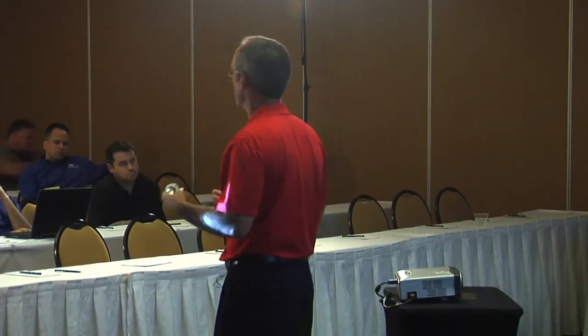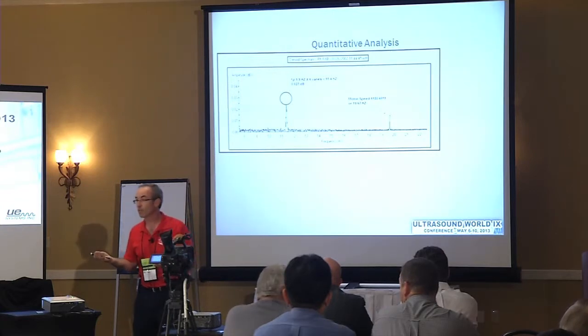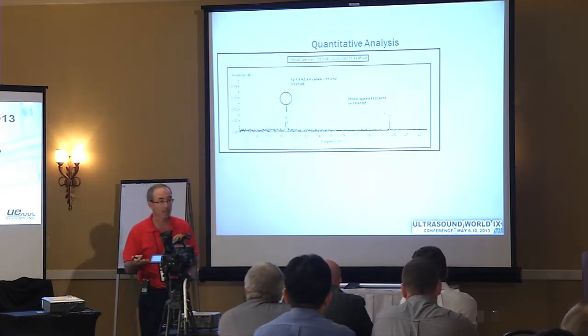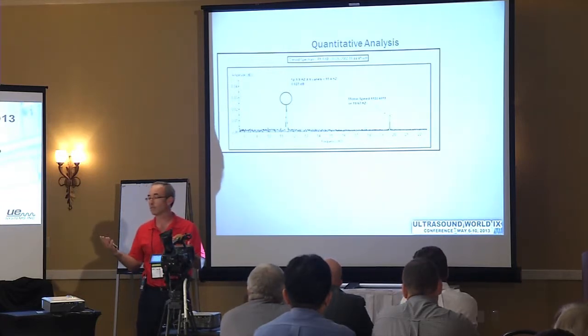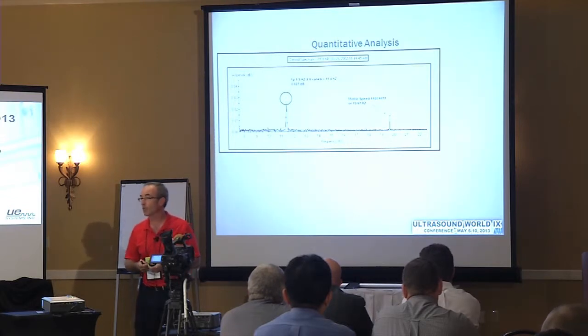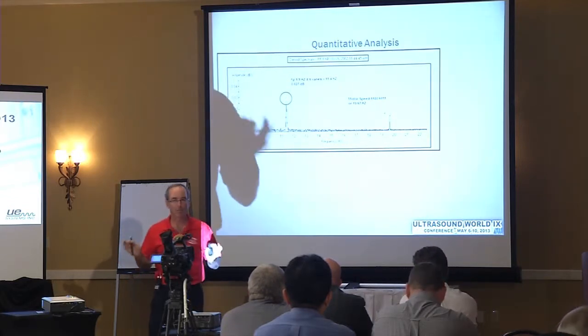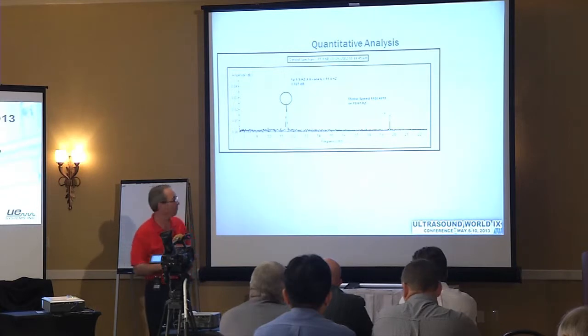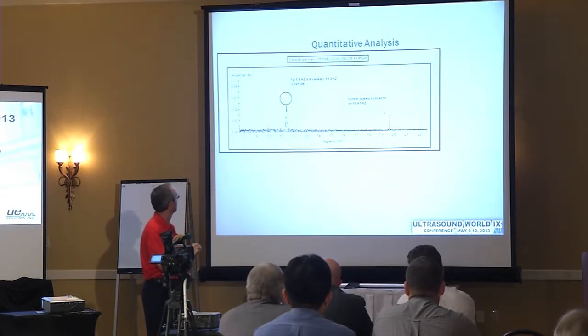Now what could go wrong with your vane pass, for you vibration experts? What does it indicate if it starts to rise in elevation? Balance problem, maybe a damaged vane, some type of impingement that may be occurring. So all mechanical related stuff, again we're going to give a number, and it can be trended.